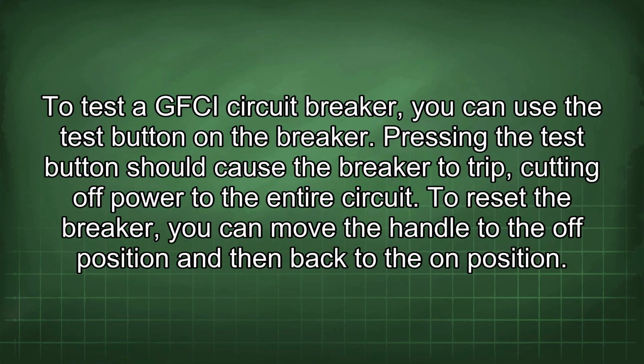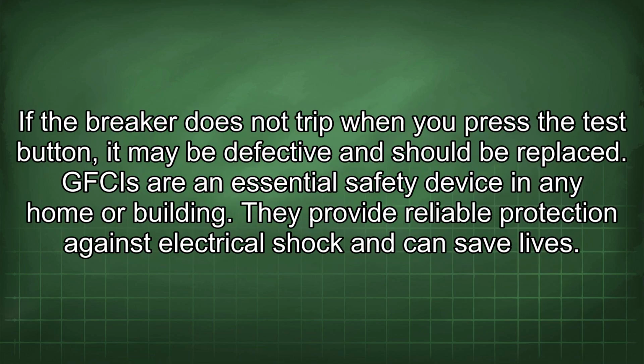To test a GFCI circuit breaker, you can use the test button on the breaker. Pressing the test button should cause the breaker to trip, cutting off power to the entire circuit. To reset the breaker, you can move the handle to the off position and then back to the on position. If the breaker does not trip when you press the test button, it may be defective and should be replaced.